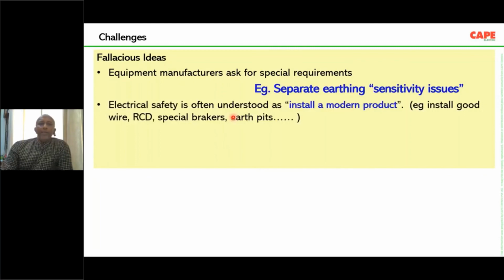And when we talk about safety, people always say, oh, we have a device, probably this device didn't trip, so you replace the device, you put a new device and you achieve electrical safety. This is also wrong. Electrical safety is often understood as installing a modern product by which you get safety. Say, for example, you use a good quality wire, not a class 5 wire. Always the wires are class 5, but people say instead of FRS wire, you go for FRLS wire. Basically, play with the plastic in the wire.